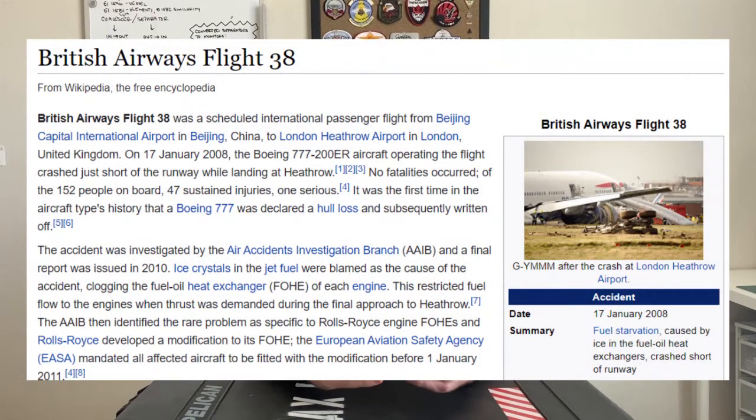So why is water contamination bad? First of all, water doesn't burn, and fuel in an engine needs to combust and provide thrust. Specifically with aircraft at high altitude and extreme low temperatures, any water present in the fuel is going to freeze. Ice crystals can clog fuel lines and fuel filters, and there have been aircraft that have crashed because ice crystals formed in the fuel system and starved the engine of fuel. Water can also lead to other forms of contamination: when water sits long enough, things will start to rust, leading to microbiological contamination. That rust can lift paint or epoxy coatings in tanks, leading to particulate contamination. And if you leave water sitting long enough, things are going to start growing in it — other forms of microbiological contamination.